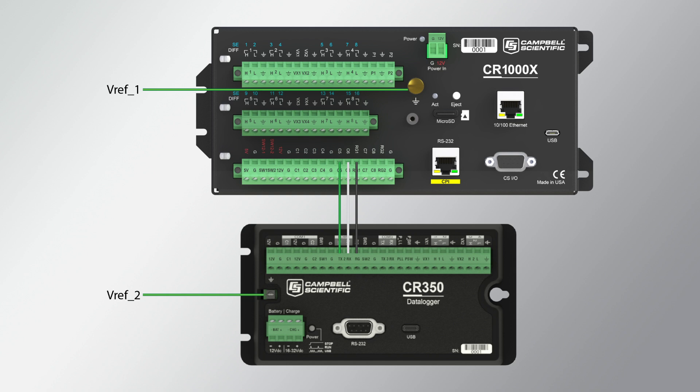If the black wire were connected to a G channel on each data logger, the ground lugs would be connected to two different grounding rods and a ground loop would be created.